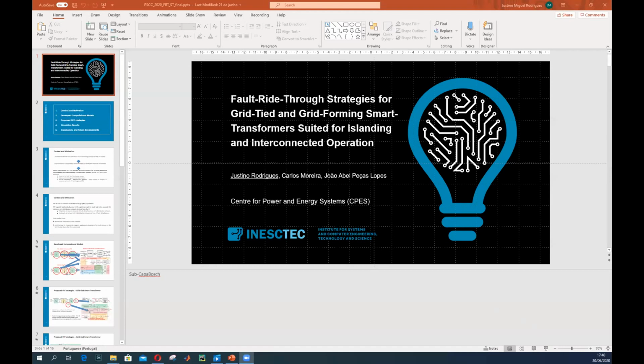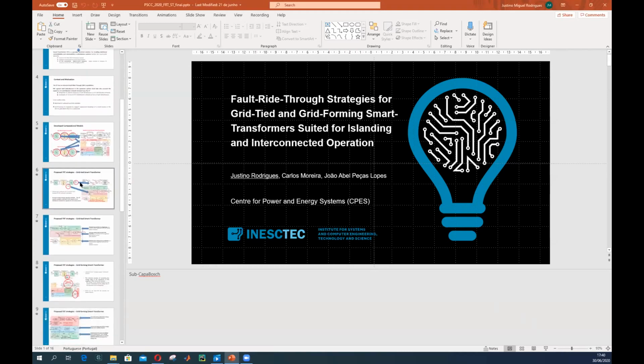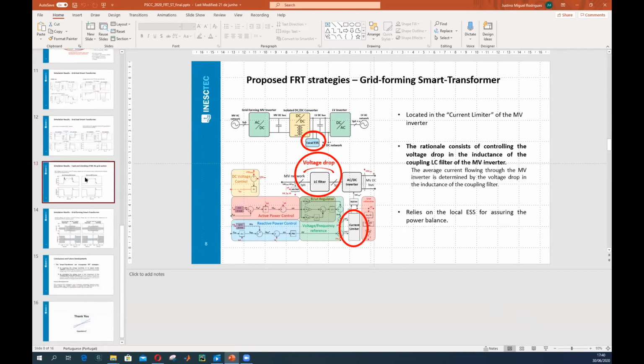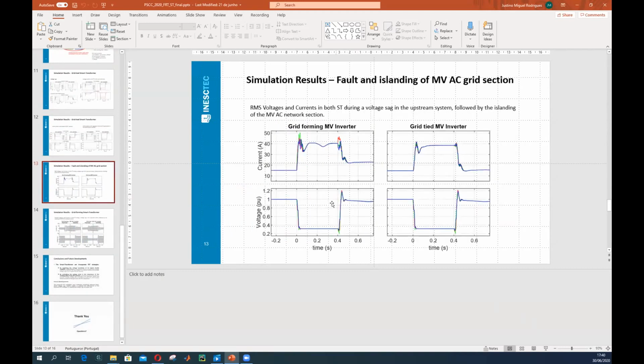Okay, you see that after the sag, the voltage has a small droop, and I was wondering if you simulated longer times to see if it is not steadily falling down. Now we have it. I figured it out. I don't know the number of the slide, sorry for that. If you see in this figure, the phase voltage is starting to fall down, and it seems that there might be some low frequency oscillations. And if you consider that you should be around 0.95 to assure that you have ride-through capability, have you checked on that, or have you even considered that kind of problem?